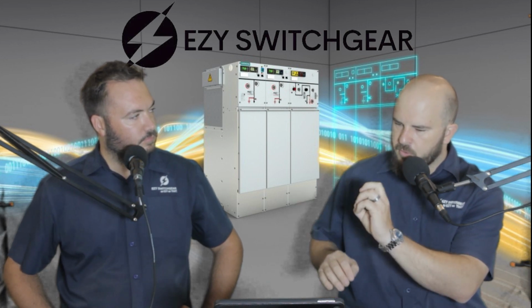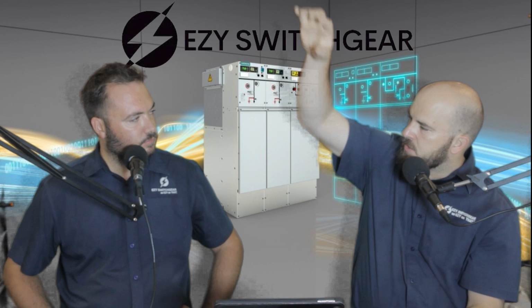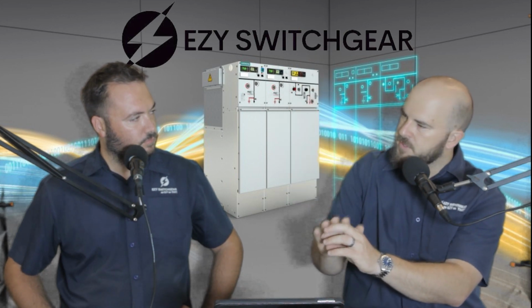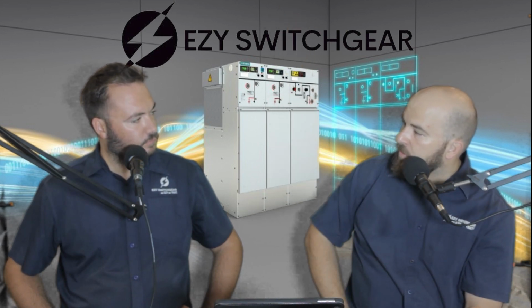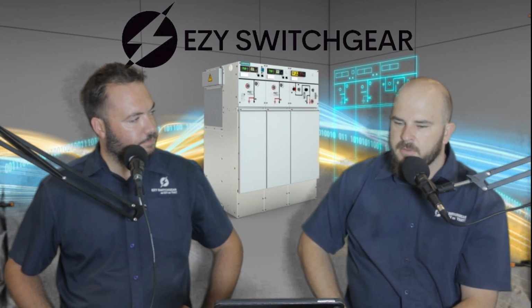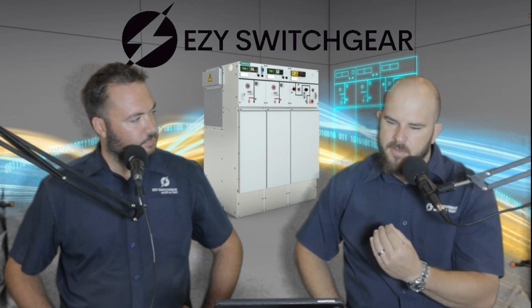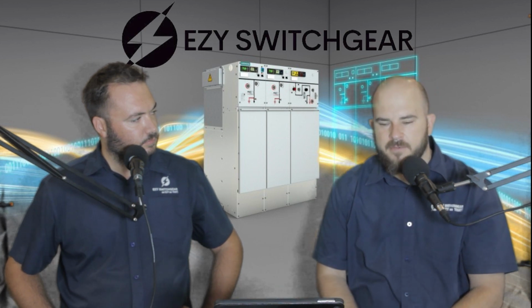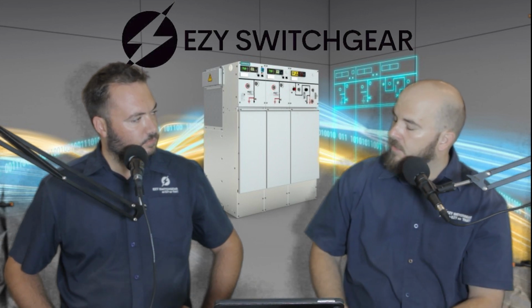to the source. So it will say that this one will trip on, let's say, 10 amps before the next one on 100 amps will trip, before the next one on 1,000 amps will trip. So that when you have a small fault, the first line of defense will trip. Because you can imagine if you plug in something faulty and it takes out the whole neighborhood, not everyone is going to like you very much. Yeah. So switchgear have got the job of discriminating the fault down to the smallest piece of outage. And that helps to keep the whole system safe and reliable and stable.